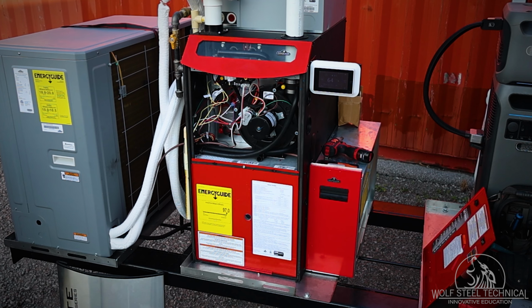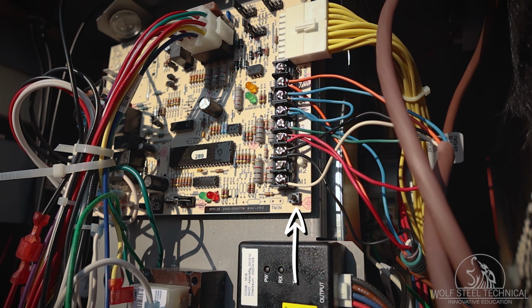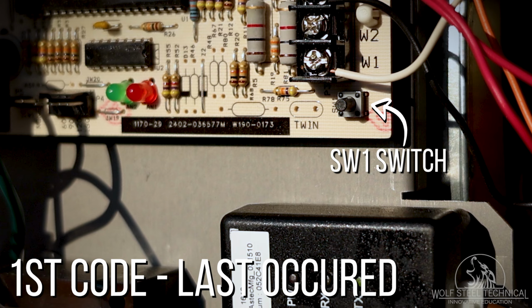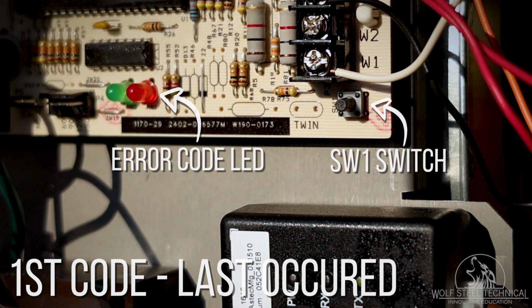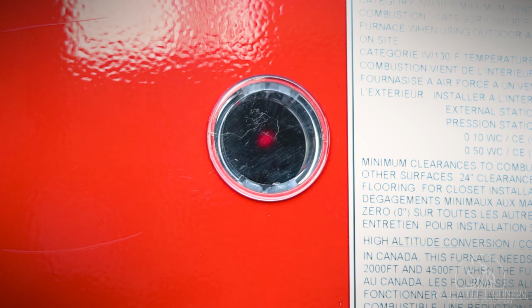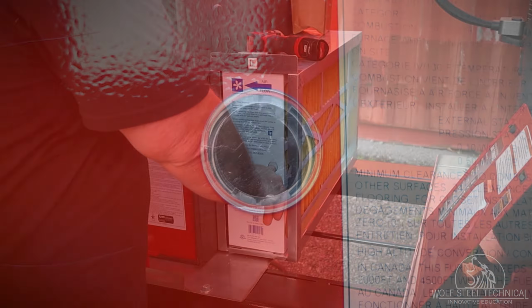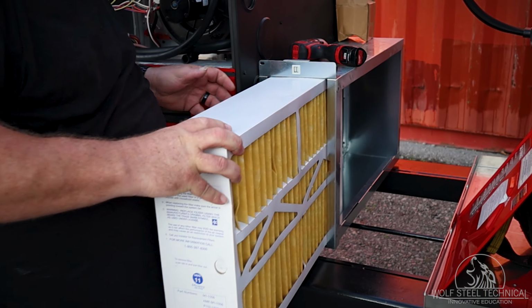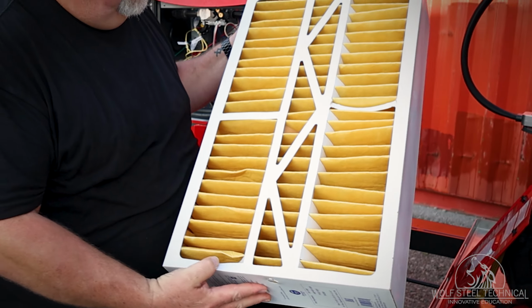With the lower door removed, use SW1 to display the last 5 error codes. The first code displayed will be the last code that occurred. The error code LED is red and will flash a number of times depending on the error being experienced. After checking the error codes, check the filter for clogs and replace as required.